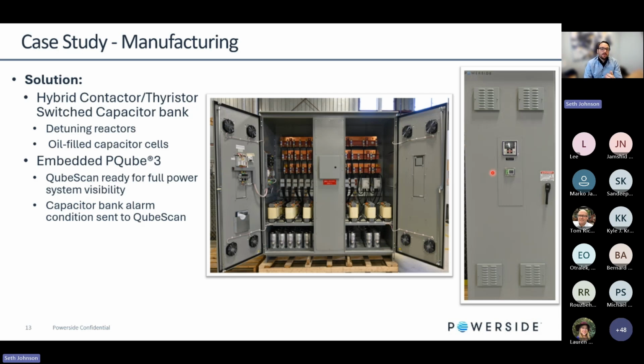And then we even took it a step further by wiring the alarm contacts inside the controller directly to the PQube. So if an event or an alarm occurs on the capacitor bank, such as a blown fuse being detected or an over voltage condition, it will send a signal to the PQube, which then gets sent back up to QubeScan, and they'll get an alert directly to their email that there's an event that's taken place, and they need to go take a look at the capacitor bank. And this is certainly good for them, because they did not necessarily have a robust maintenance staff there that knows much about this product. So this is just another way we were able to provide some additional value to this customer.